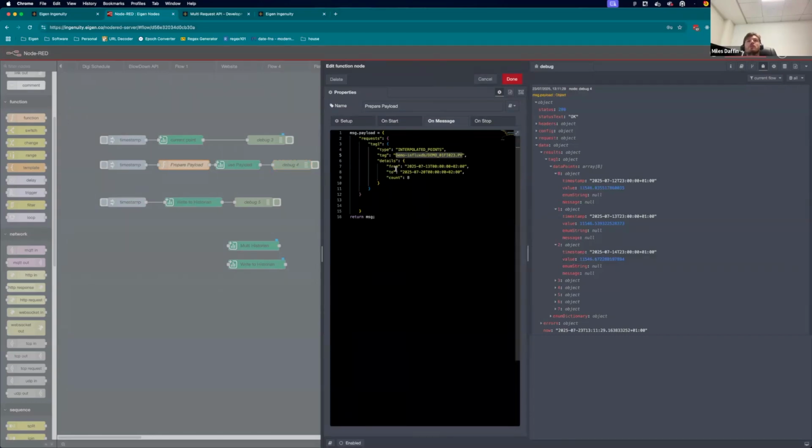So then what you could do is set your start time to when the valve opened, and then maybe say 30 minutes after, and then you could configure the count so that you might get a point a minute, a point a second, or if you know that the tag is quite detailed, you might ask for raw, and then you could run a loop statement through that, and you could then track how long it took for the valve to depressurize below 7 bar or below 50%. And then with that data, you could store it into an object in Node and then write it somewhere else or move on to the next step.